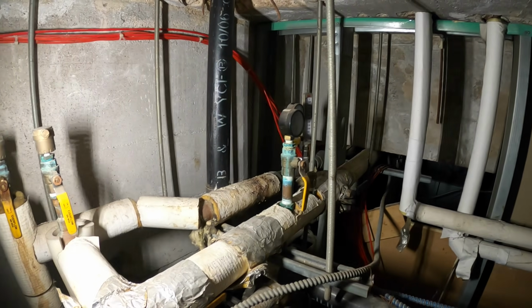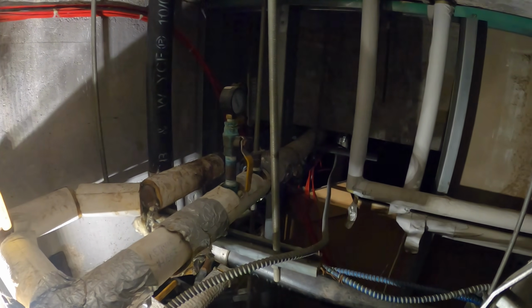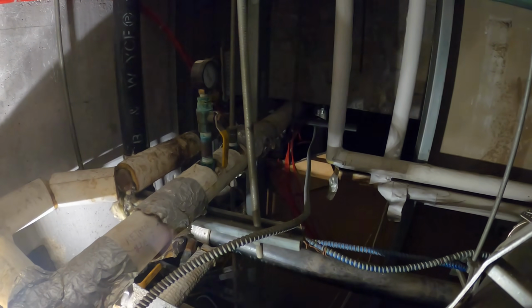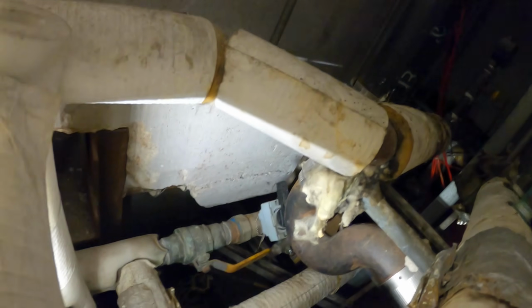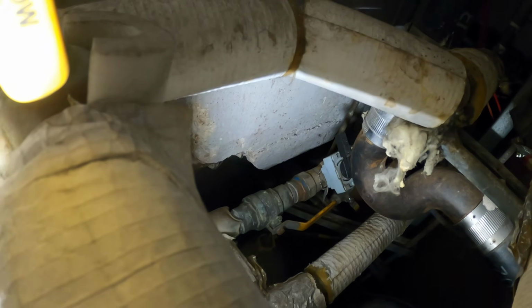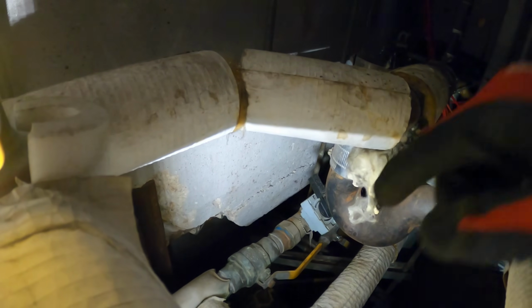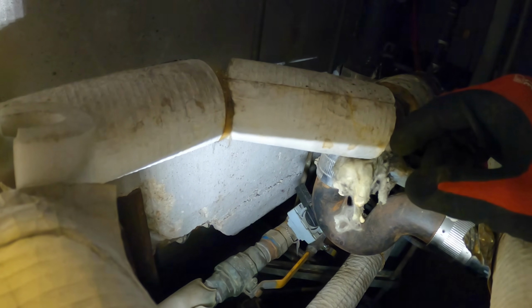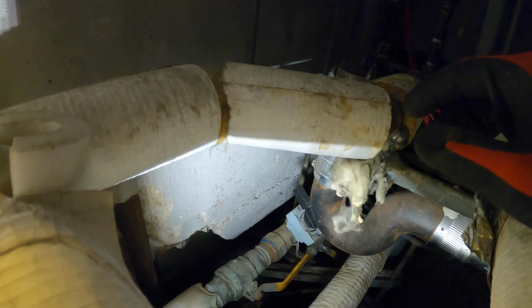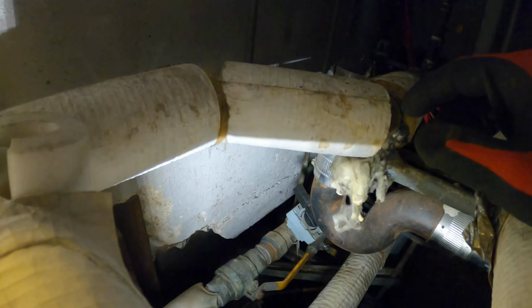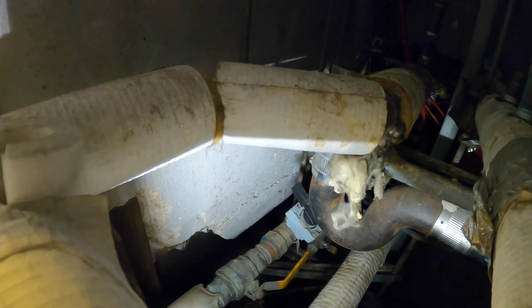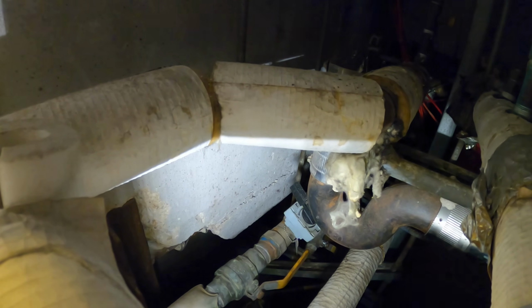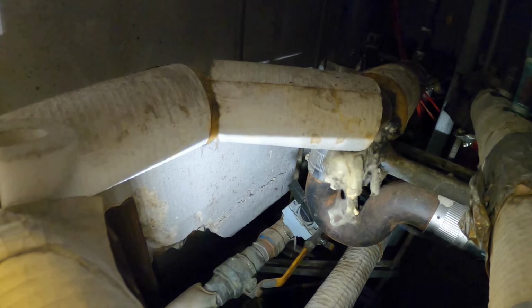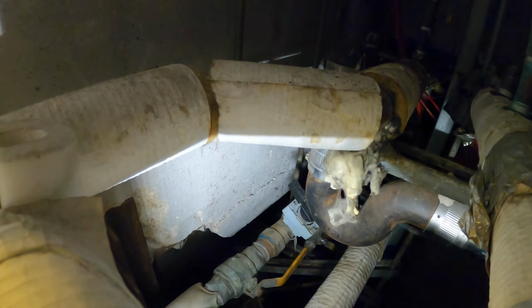All right, let's put the system in heat. I want to watch this, see if that actuator handle moves, this piece right here. Put it in heat, raise the temperature to 80 max. When the fan starts, this heating actuator should engage.